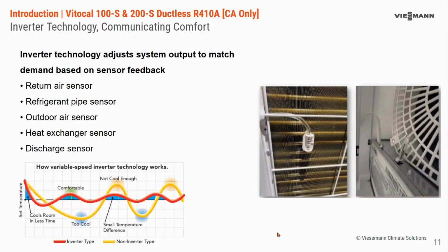A little bit on the inverter technology that we've been mentioning. The indoor unit and the outdoor unit communicate based on a series of sensors: return air, refrigerant sensors, outdoor air, and the sensor on the heat exchanger, which depending on which mode it's in. That's why it's called the heat exchanger sensor, not condenser or evaporator sensor, because when you're in heating and when you're in cooling, they're considered different. But using all those sensor inputs, the system is able to more precisely maintain temperature. So that red line is the inverter compressor, with much less over and undershooting and more consistent runtime, because most of the energy is consumed on startup for non-inverter type systems. This yellow line would be representative of a traditional single or two-stage heat pump without a variable speed compressor.